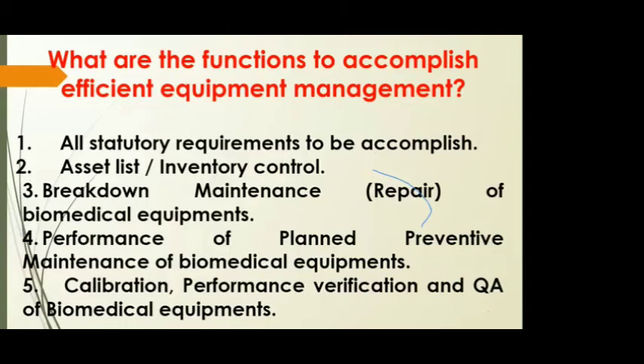And next is the calibration, performance verification, and quality assurance. As you people know, calibration of the equipment is a must, and once a year we need to do the calibration of the equipment. If you have the tools in your department, it's well and good, you can do the calibration of all the equipment. If not, then we need to call a third-party service to do the calibration, and we need to ask for the traceability of the particular equipment, and give one copy to the end user and keep it safely.